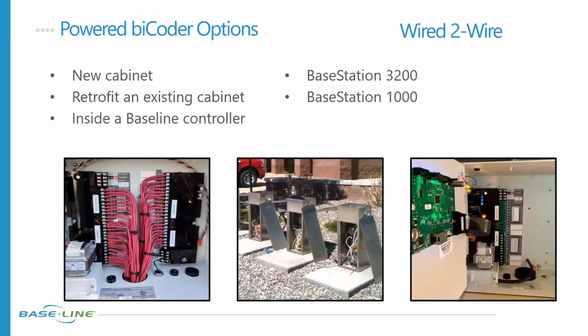All they had to do was, in a half-inch conduit, run one section of 2-wire to connect those power decoders together and daisy chain them, because the power decoder is just another 2-wire device. So they didn't move any wire around, they just extended it with a small 3-foot section of 2-wire.